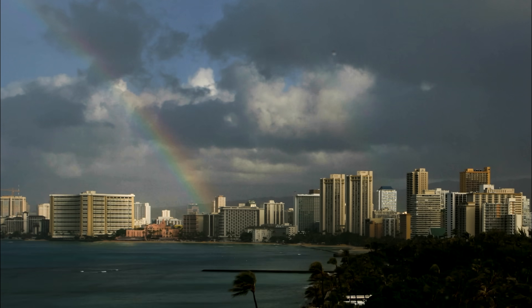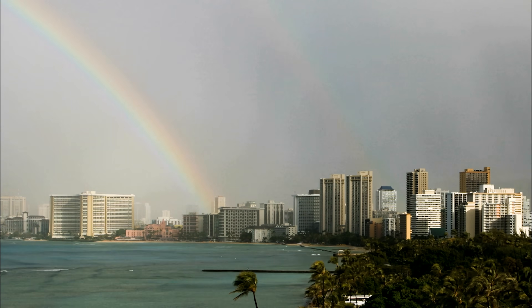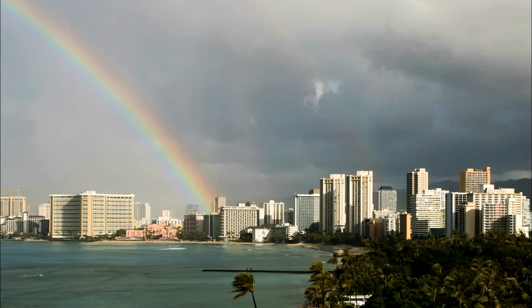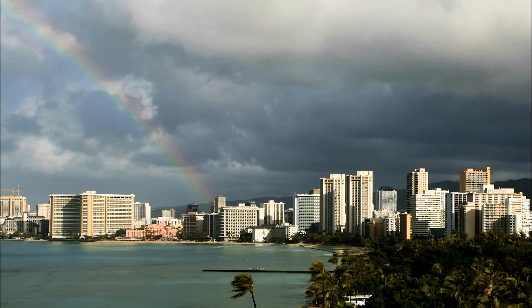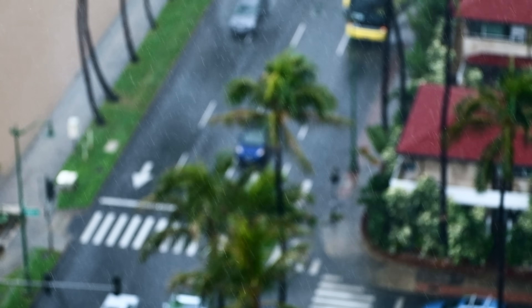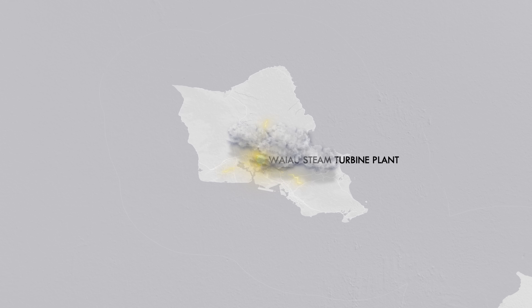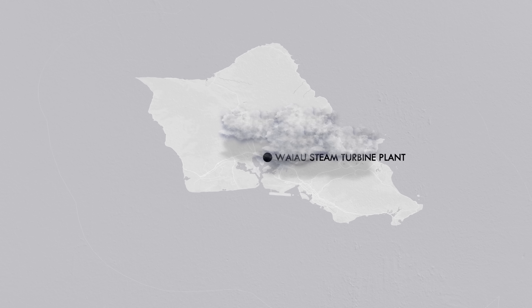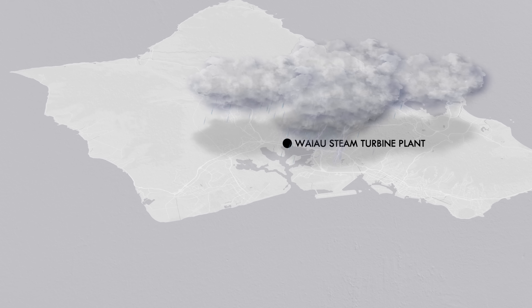In January of 2024, right on the heels of a serious drought across the state, a major storm slammed into the Hawaiian Islands of Oahu and Kauai. Severe wind caused damage to buildings, and heavy rain flooded roadways. At the Waiau steam turbine plant, the rain reached some of the generator unit controls, tripping two units and knocking 100 megawatts of power off the tiny grid — roughly 10% of demand.